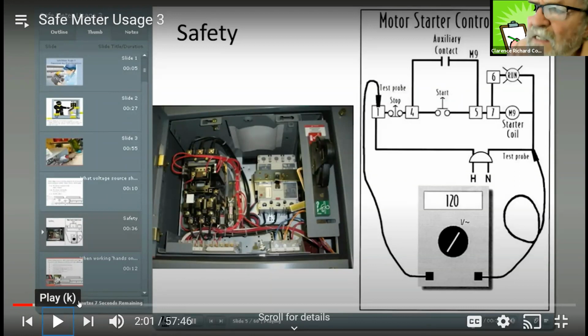Okay, so look in here, I'm not seeing a transformer in here. There could be one under that. There could be a transformer right there. And a lot of times they'll put fuses on that. That means if I flip this off, it not only takes away my 480, it takes away the 110 volts that would take in order to energize what you have here.